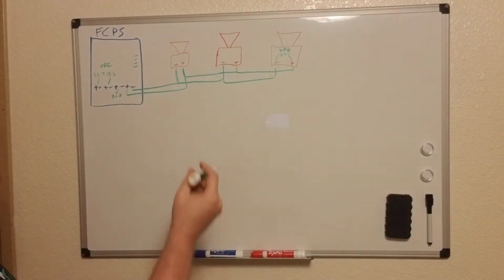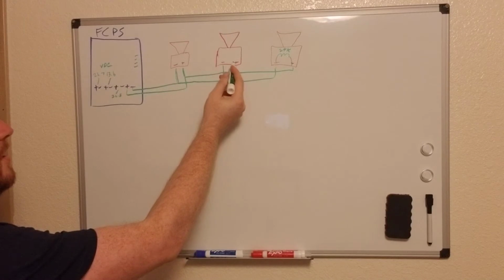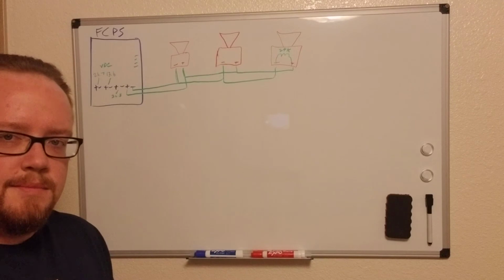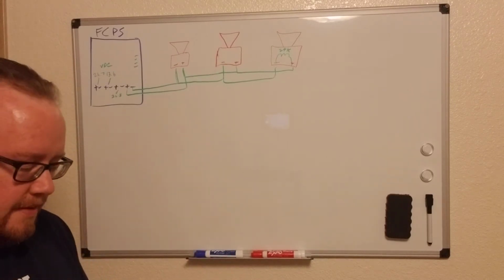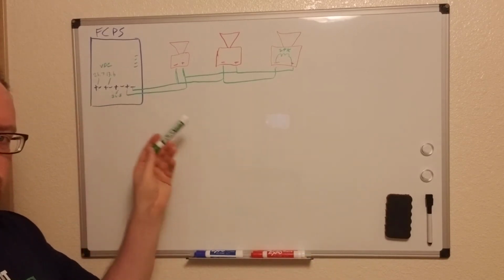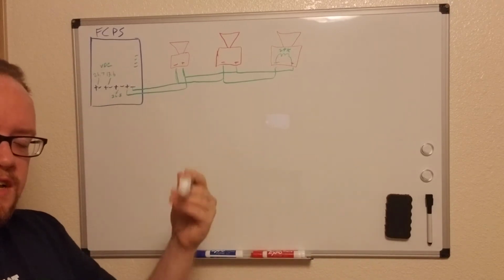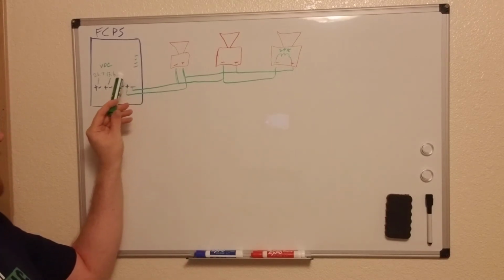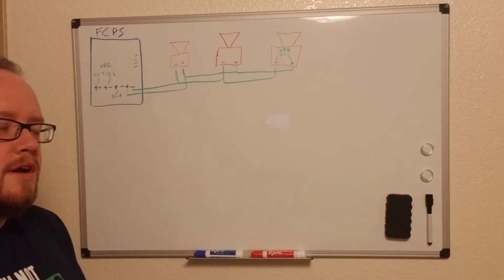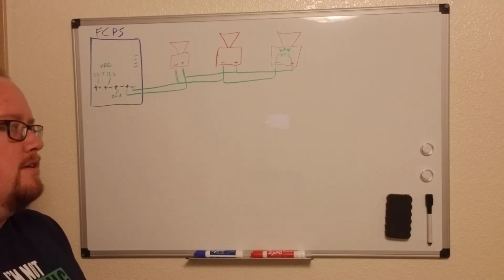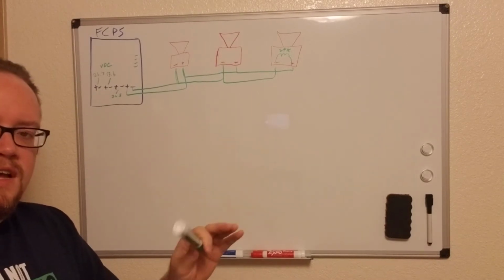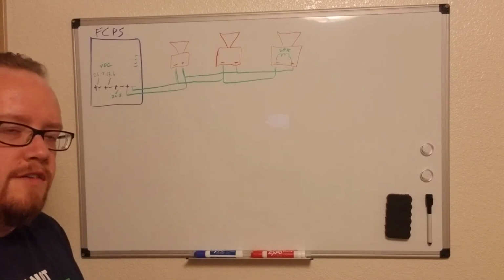So somewhere out there, there's a connection between these 2 wires, or it's crushed and the conductors are touching each other in the same cable, and then the voltage is unable to get to the end of the line. And so the panel will see the difference between an open or a short, and it will adjust that voltage. So as long as you know what voltage for that particular panel should be, then you're good. And first thing you do is you put your meter on the normal circuits, the circuits that are not in trouble, and then that tells you what you need to be looking for.